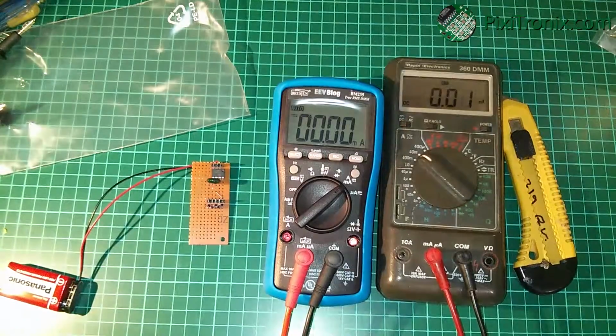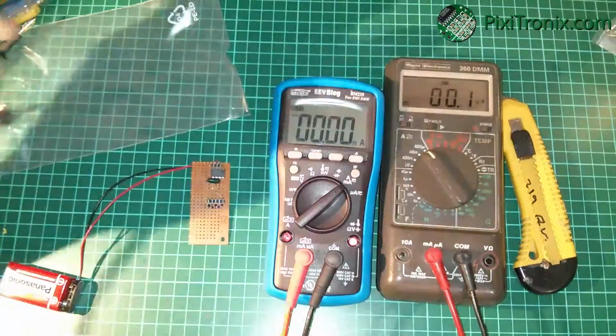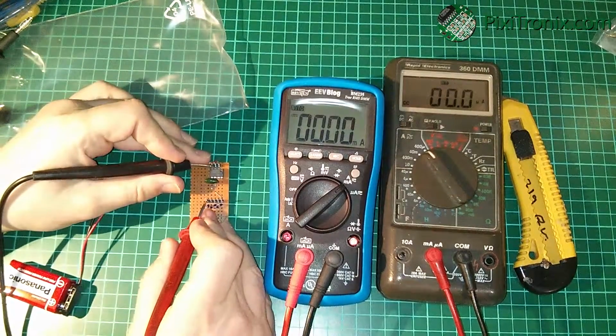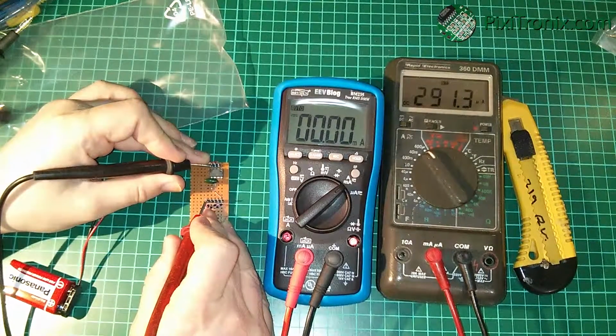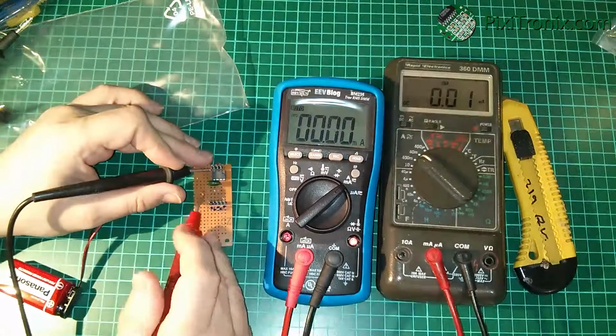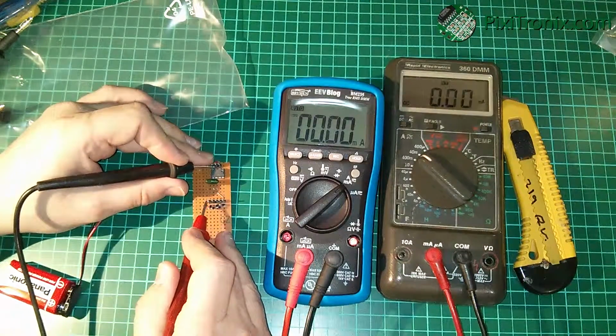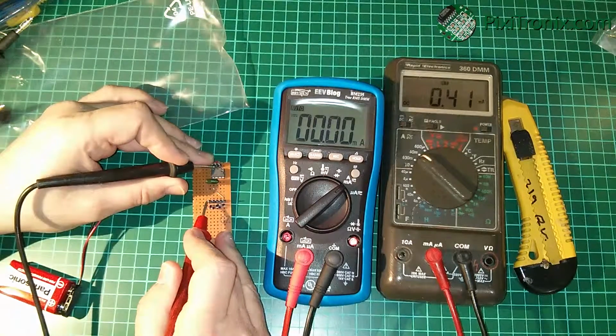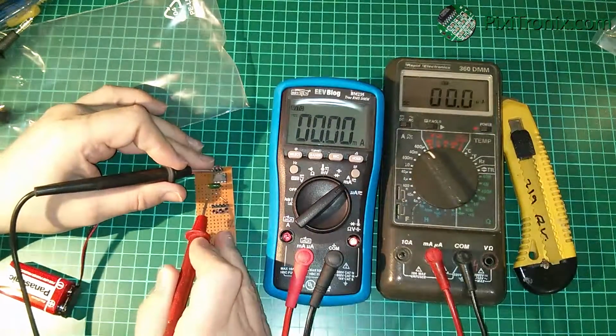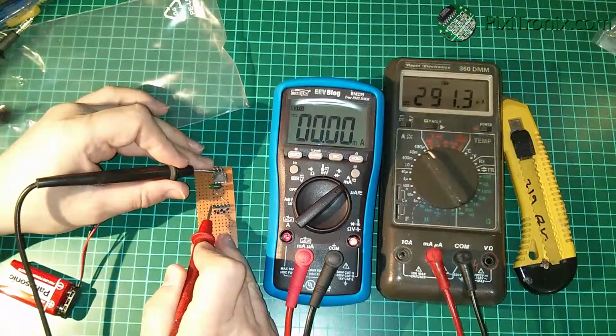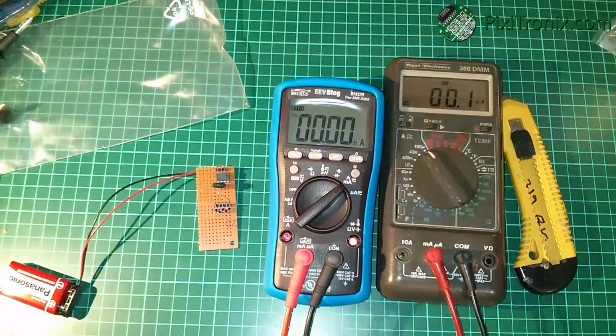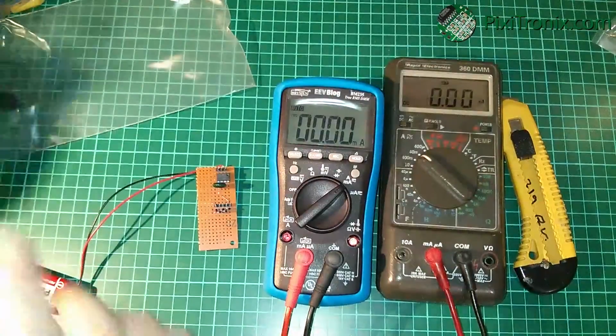I wonder if it's a ranging issue. Let's go down to that - it's going to be over scale, but we'll see how it measures. Could be calibration, just a wee bit out. Yeah, so it looks like on this old meter the microamps range has just gone crazy. We've got 0.41 milliamps, and if I go down to the microamps, 291 - so it looks like the microamps range has gone wrong on that old meter.